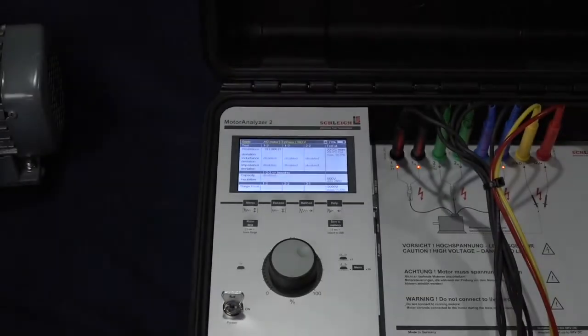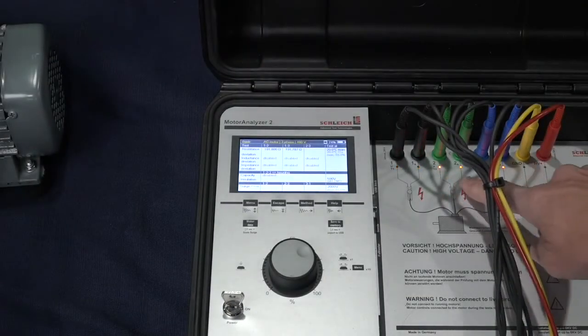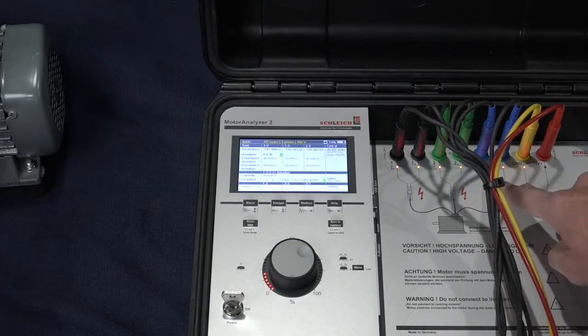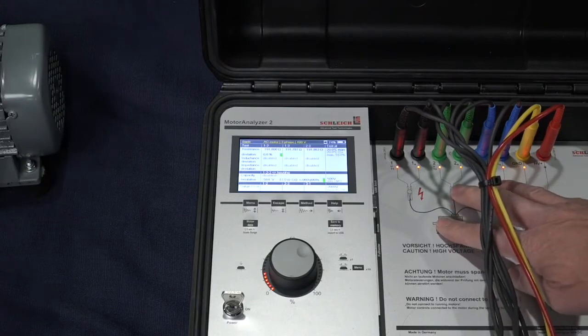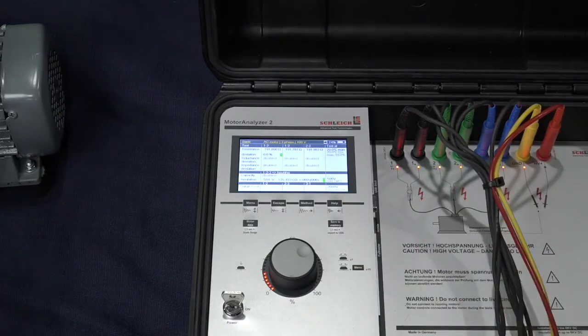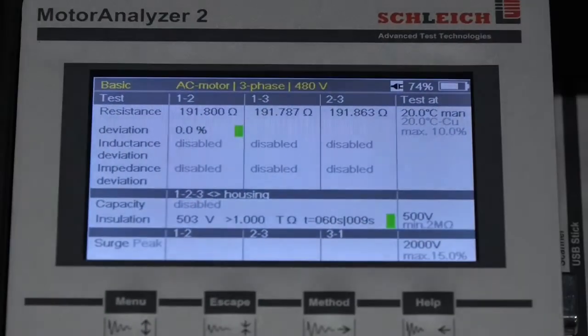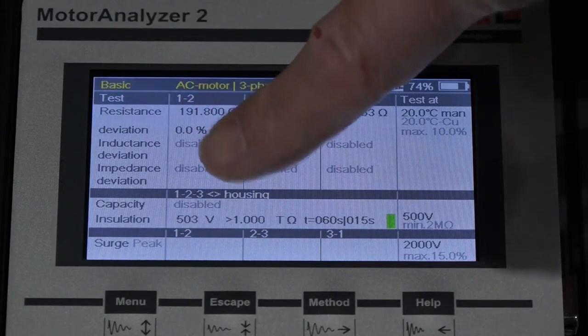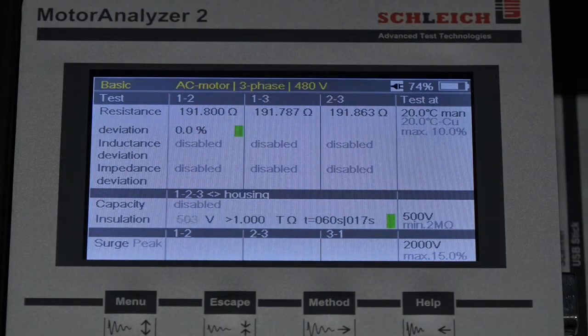If we back out, we can see over here on the test leads we have LEDs illuminated in front of each test lead that's active. So we saw a moment ago it did the resistance test. Now it's doing a DC megohm test. Let's zoom in on the screen so you can see that. Here we have our 3 resistances that we measured, and we've jumped right into an insulation resistance test. This is a 60-second test per IEEE 43. At the end of this, it will acquire the insulation resistance and have that available to save. When it's done with this test, it'll step right on into a surge test.